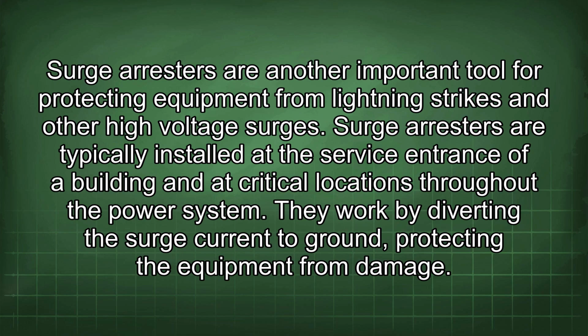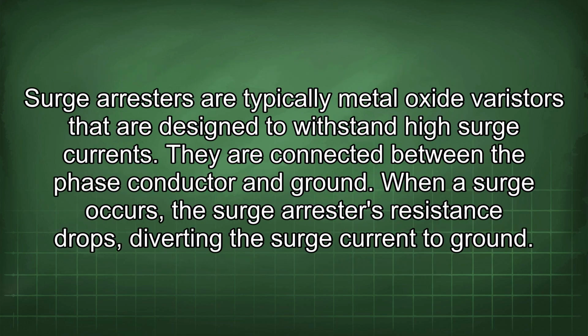Surge arresters are typically installed at the service entrance of a building and at critical locations throughout the power system. They work by diverting the surge current to ground, protecting the equipment from damage. Surge arresters are typically metal oxide varistors that are designed to withstand high surge currents. They are connected between the phase conductor and ground. When a surge occurs, the surge arrester's resistance drops, diverting the surge current to ground.